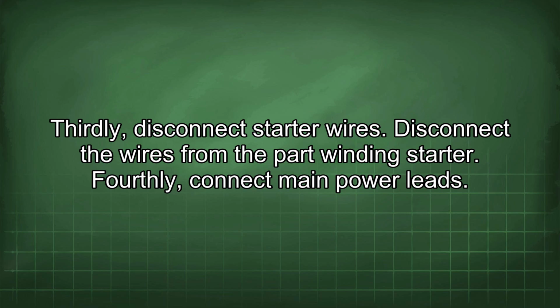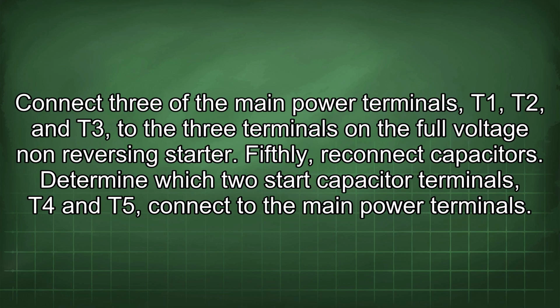Fourthly, connect main power leads. Connect 3 of the main power terminals, T1, T2 and T3, to the 3 terminals on the full voltage non-reversing starter. Fifthly, reconnect capacitors. Determine which 2 start capacitor terminals, T4 and T5, connect to the main power terminals.